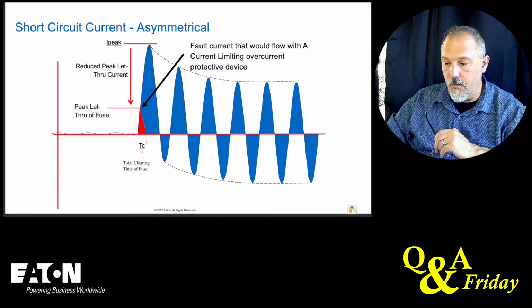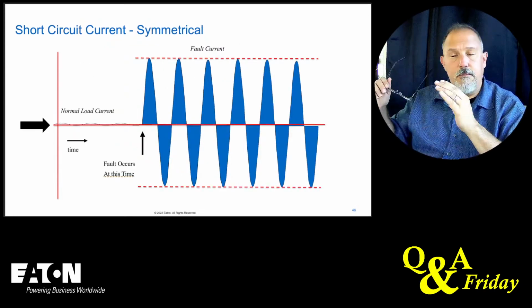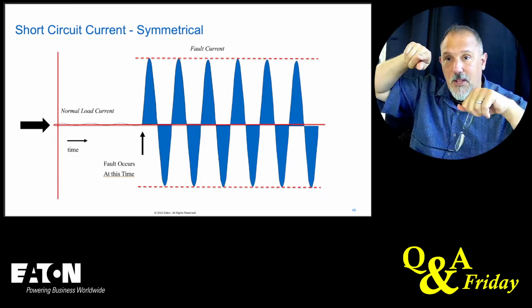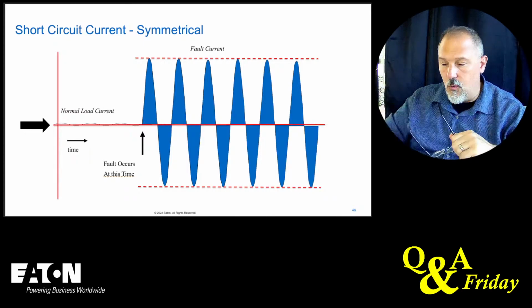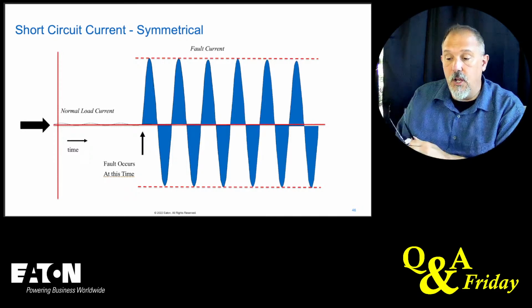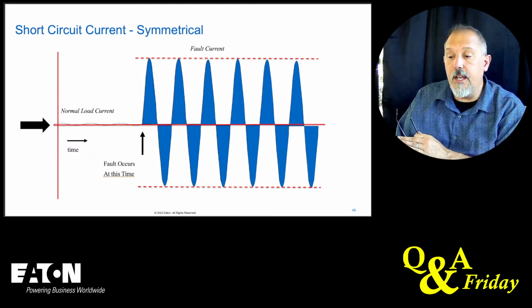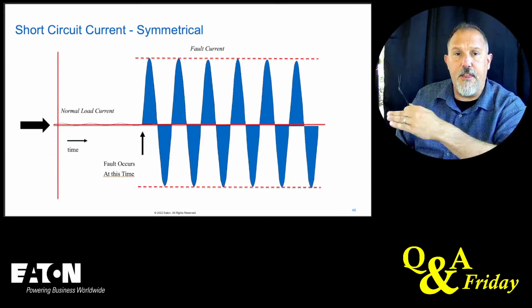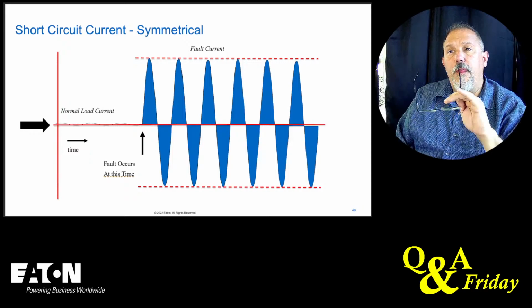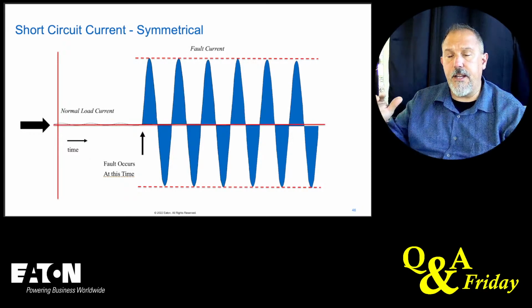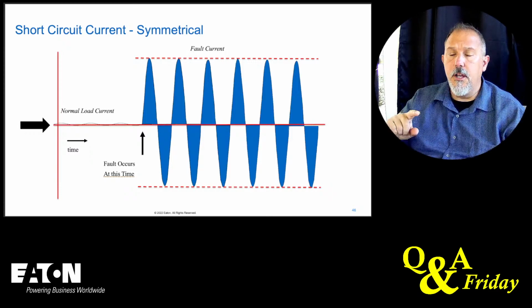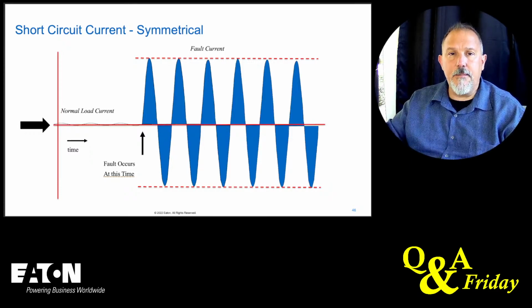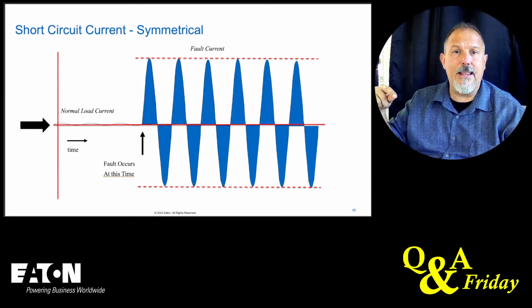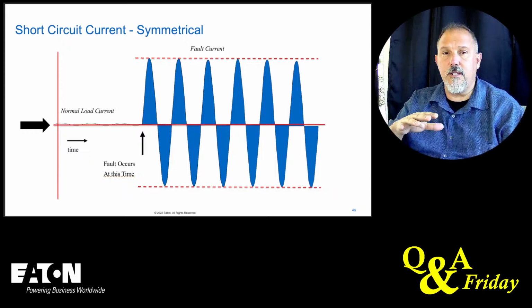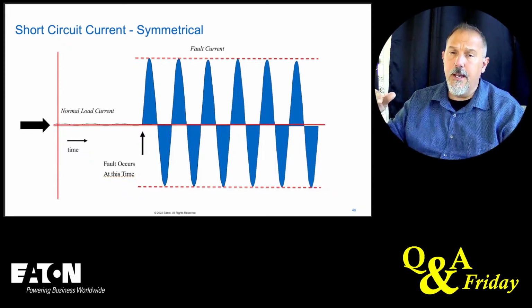A symmetrical waveform looks like this. Okay, so this is a symmetrical waveform, meaning the humps on the top equal the humps on the bottom. A symmetrical waveform is the value that we calculate when we calculate fault currents. When we're doing a short circuit study and short circuit calculations, we're calculating that value. Then you can do a couple different things. I've seen engineers, and I believe there are some IEEE standards, that say you could take 1.6 times that symmetrical ampere value to get the asymmetrical value. But in most cases, we're going to calculate that asymmetrical value based upon an X to R ratio, which we're going to get to.